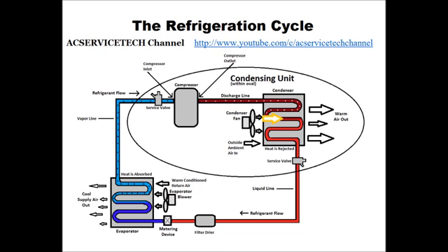A saturated state is where vapor and liquid both exist at the same time. Right after the saturated state, it turns into a complete liquid, and until it comes out right next to the service valve, the temperature decreases as it's rejecting heat. The temperature decrease in liquid form is called the subcooling. The saturated state is where it's transferring most of its energy. The refrigerant is what is carrying the heat and moving it, rejecting it and absorbing it, and most of that energy transfer occurs right in that saturated state.